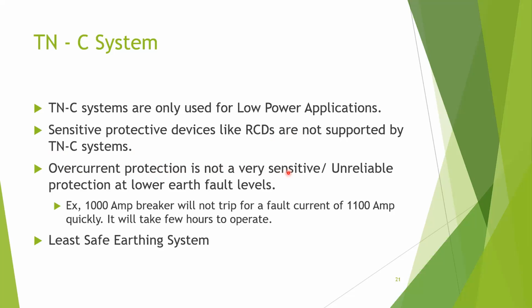As I mentioned earlier, a 10 ampere breaker will not trip for 11 amperes instantaneously. It will take a few hours to operate, because if you consider a time curve, we will learn about them in upcoming lectures. If you have a 10 amp breaker, it will start to trip at 1.45 times the rated current. So if it is 10 amps, usually it will trip at 14.5 amps at a finite time limit. It will trip at 11 amps, but it will take a few hours, so we are taking that as infinite time. So using overcurrent protection as a tripping circuit for earth faults is not very good. That is one of the major disadvantages of the TNC system.